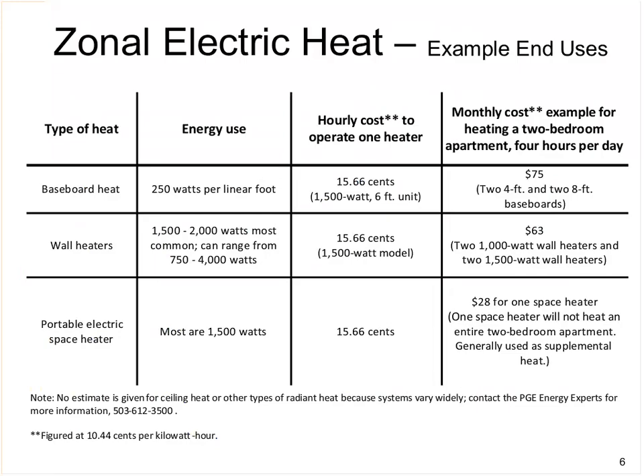So there are a number of different types of zonal electric heating systems, and here are some examples and uses. A baseboard heater is about 250 watts per linear foot. The hourly cost to operate a 6-foot, 1,500 watt unit would be about 15.66 cents. And moving towards monthly cost for a 2-bedroom apartment, total cost might be $75, and that might be represented by two 4-foot and two 8-foot baseboard heaters.